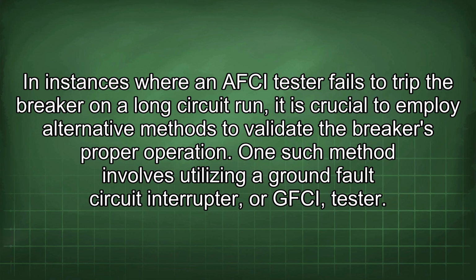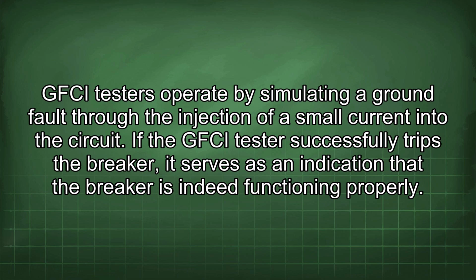One such method involves utilizing a ground fault circuit interrupter, or GFCI tester. GFCI testers operate by simulating a ground fault through the injection of a small current into the circuit. If the GFCI tester successfully trips the breaker, it serves as an indication that the breaker is indeed functioning properly.